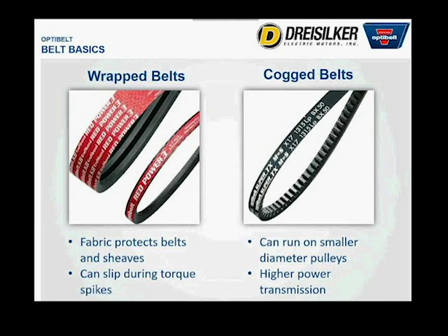In addition, one of the advantages of wrap belts is that it can slip during torque spikes. This is mostly for if you're dealing with a gasoline engine where the torque can go up and down and you can have changes in the load, not so much like fans in the HVAC industry. What that fabric does is it allows it to slip, and the fabric takes a little bit of damage, but not a lot, thus letting the belt last longer in applications where this happens.